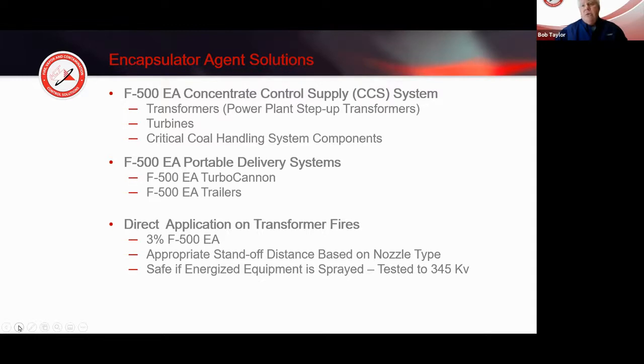There are also portable delivery systems like the turbo cannon, and trailers and skid units available for direct application on transformer fires or other scenarios, and even manual firefighting. By the way, no special nozzles needed like with foam - that's another savings in cost, because foams make bubbles, you have to aerate that, you have to have a special nozzle to do all that. F500 is not required to do that.